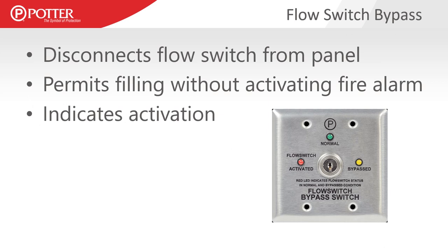There are options to avoid that. Potter offers a flow switch bypass switch that connects in line between the flow switch and the fire alarm panel, simply disconnecting that signal as it's being sent. It permits filling and maintenance without activating the fire alarm, but also gives you an indication through an LED light that it is activated. When the bypass switch is in the bypass position, the fire alarm panel goes into trouble — so it can't be forgotten about. The red LED illuminates to tell you when the paddle is in the flow position, giving you a way to test the switch without activating the fire alarm system during maintenance and filling operations.